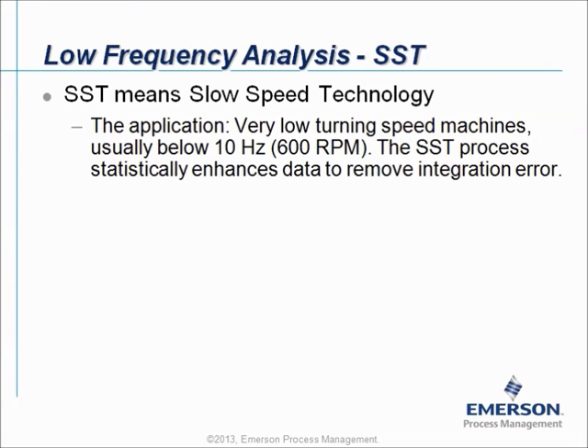Low Frequency Analysis, also known as SST, means slow speed technology. The application is for very low turning speed machines, usually below 10 Hz or 600 rpm. The SST process statistically enhances data to remove integration error.